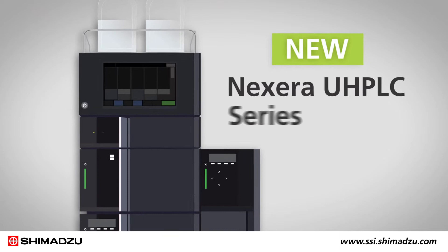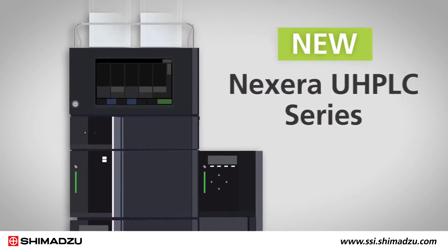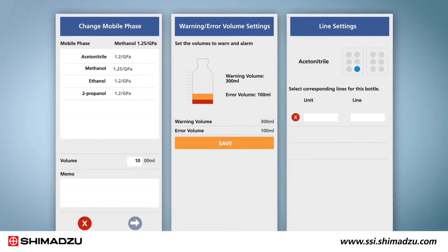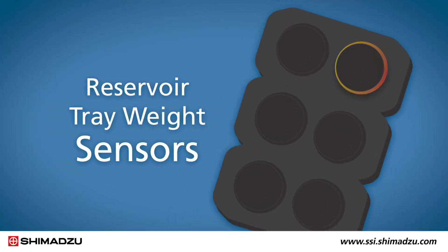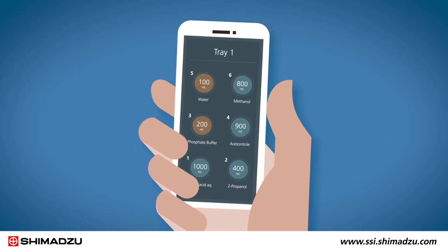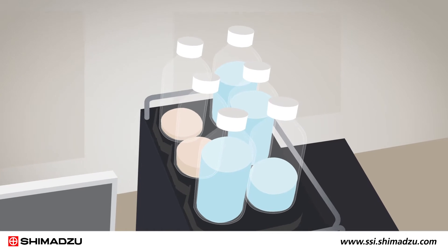Shimadzu's new Nexera UHPLC series enables real-time monitoring of mobile phase levels to ensure maximum equipment uptime. It monitors solvents gravimetrically and notifies you if there isn't enough mobile phase to complete analysis. Reservoir tray weight sensors can be used to monitor the volume of mobile phase or auto-sampler rinse solution in up to 12 containers. The containers can be checked remotely from a mobile device, so there's no need to go to the lab to check the mobile phase levels.